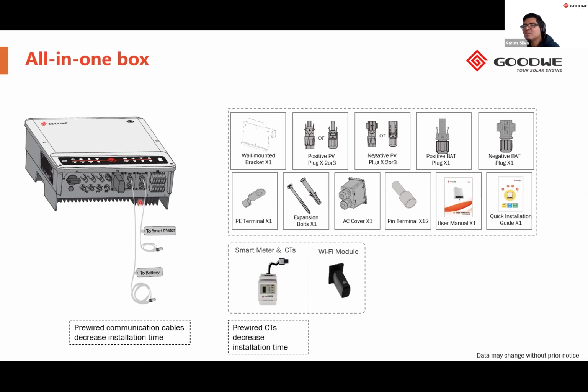The inverters do come pre-wired as well. So that means the BMS or the BMU cable, as BYD like to call it, is already connected to the inverter, and the smart meter cable is already connected to the inverter as well. So I think the smart meter cable is up to 3 to 5 meters length, and the BMS cable is up to 10 meters as well. So that should give you enough length to install the inverter. However, if you need longer cables, then you can replace them with a standard Ethernet cable with no issues.